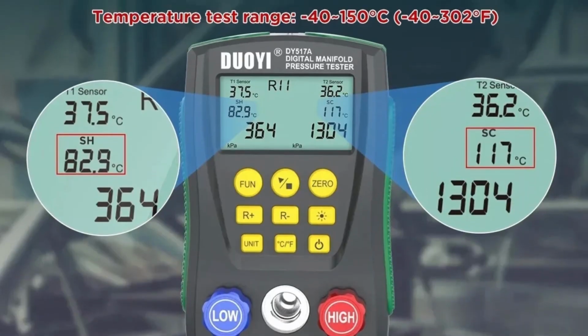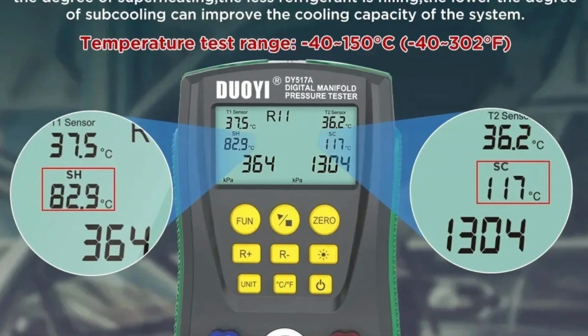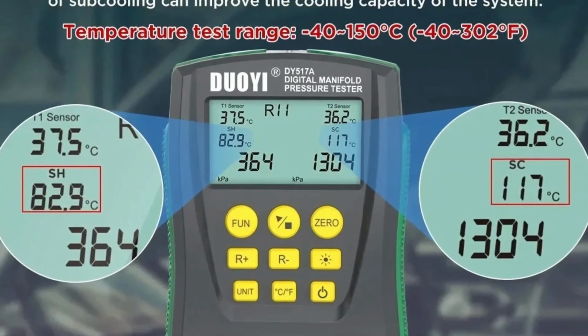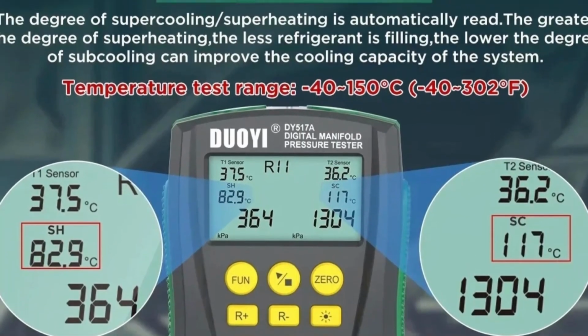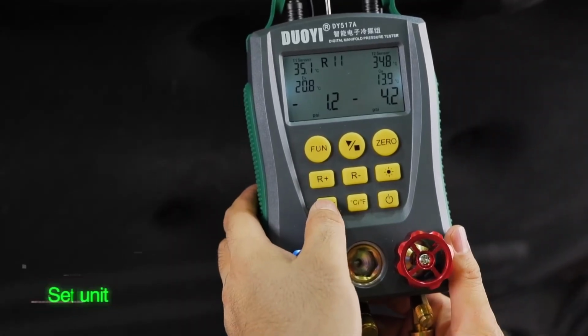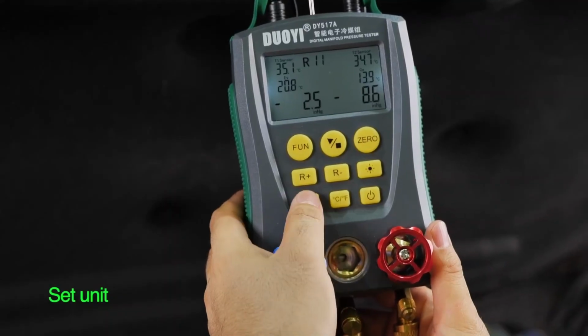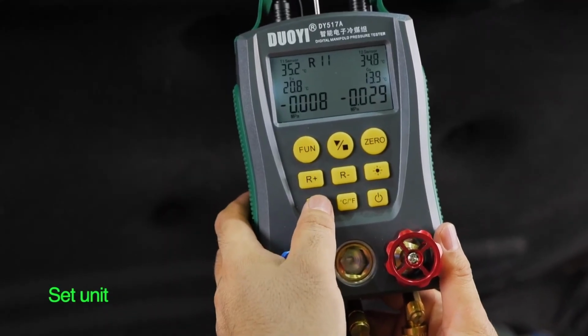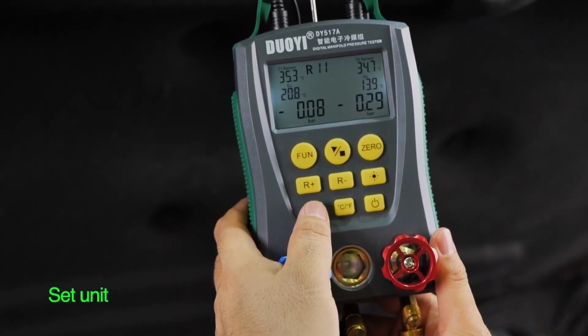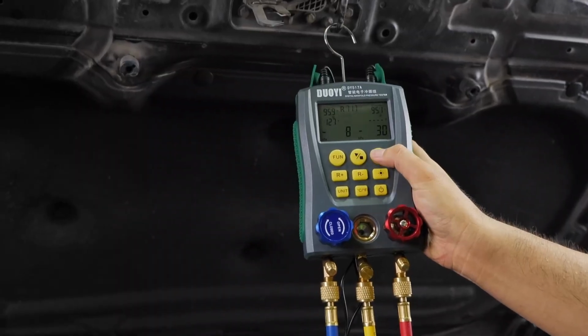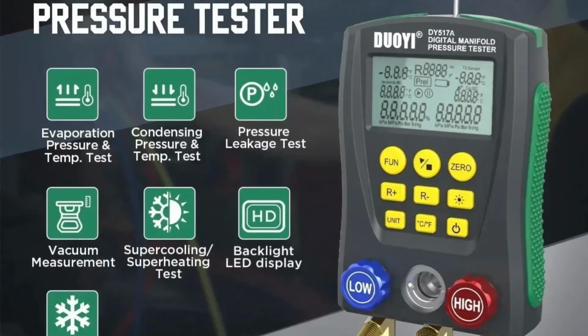Integrated temperature measurement. The temperature reading is especially useful and informative. When you analyze the behavior of the refrigerant inside the evaporator or the condenser, you'll be able to tell if the system is cooling at its peak efficiency, or if there is a noticeable loss of performance due to improper refrigerant temperature.